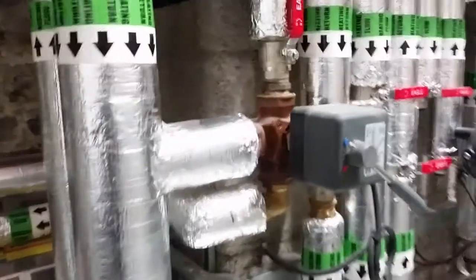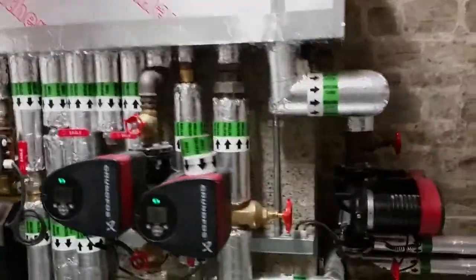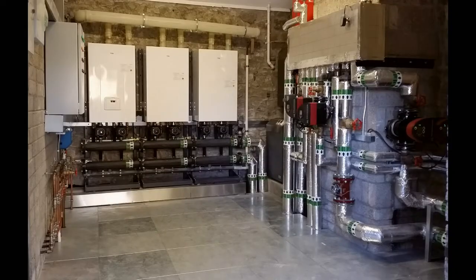So the heat coming in would come in from the heat pump collectors outside and be distributed around the system normally for central heating. And then if the mixing valve is in its second position, it would direct the water from the heat pumps back out to the gas boilers, bringing it up to full temperature. So we have now 3 gas boilers and 3 heat pumps, a primary zone with 7 subzones, a secondary zone with another 3 subzones, and there's provision for these pipes here for the future. So we're covering all future possibilities in this boiler room.